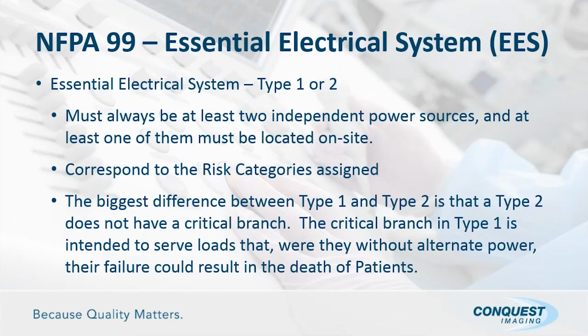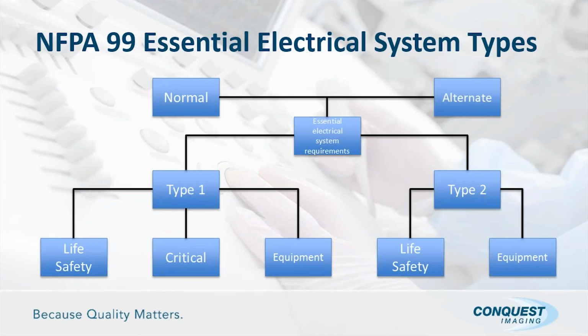It says corresponds to the risk categories assigned. In other words, type 1 is assigned to a risk category 1, and a type 2 is assigned to a risk category 2. And the biggest difference between them, and I'll show you a slide after this, type 1 and type 2, is that a type 2 does not have what they call a critical branch of care. There's 3 branches, and again, I'll give you a slide on the next one. And type 1 has the critical branch associated with it, where type 2 removes it. Type 1, if it should fail, if there was no alternate power, the failure could result in the death of the patient. So here's the slide I was referring to.